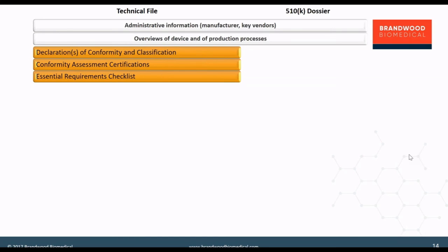If you wish your product to be marketed in a global context, it is recommended that your product be certified by a third party, that the report captures the specific requirements for the various jurisdictions that you want to cover as part of your technical file, and that the country-specific deviations or requirements are also addressed within those reports.